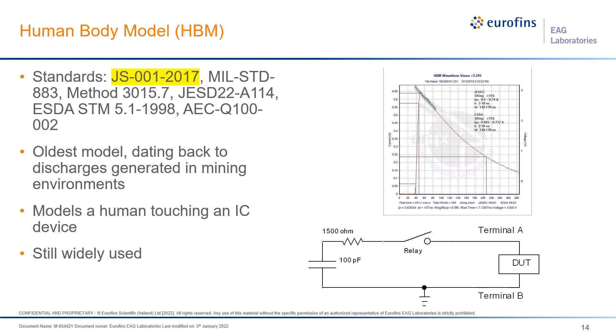When the relay closes, the ESD event is applied to terminal A, and terminal B is connected to ground. What the diagram also doesn't show is a charge removal circuit called the shunt resistor between terminal A and terminal B, so that after you've done a discharge, you don't leave any residual charges on the device.